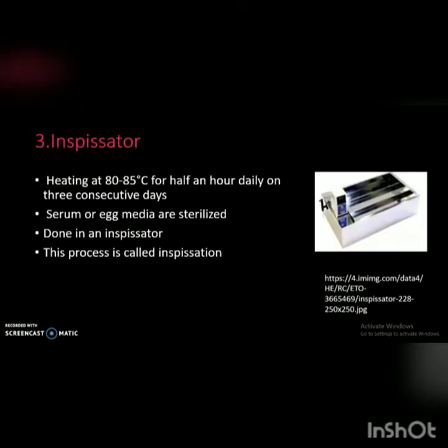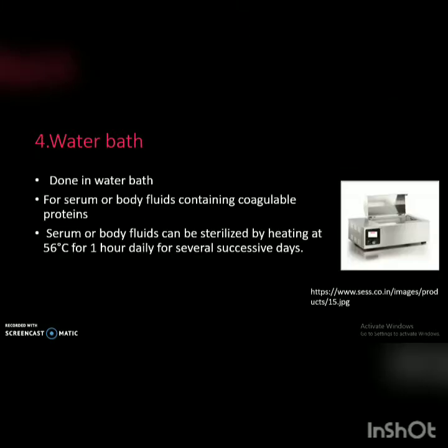Third one is inspissator. It is mainly used for sterilizing serum or egg media. Heating is done at 80 to 85 degrees Celsius for half an hour daily on 3 consecutive days in an inspissator. The process is known as inspissation.